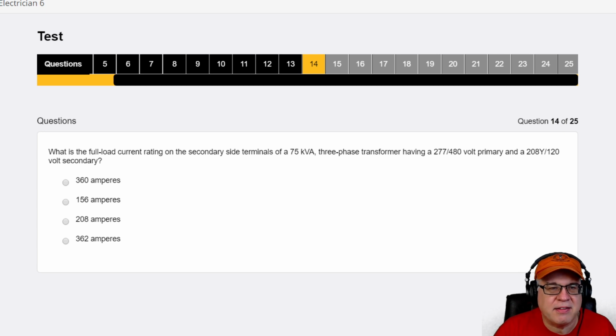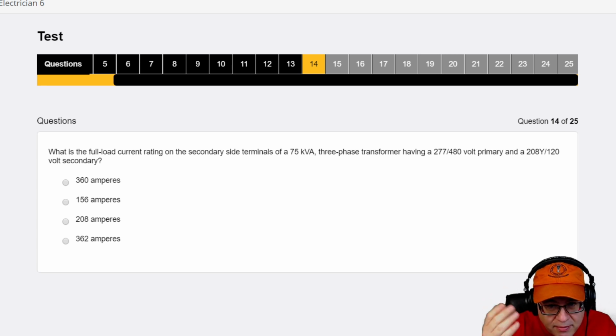It's asking about the full load current rating of the secondary, not the primary. So the secondary is 208/120, and it's 3-phase, so I've got 208. There's a shortcut to the 208 because it's 3-phase. First I'll do 208 times 1.732. Remember, 1.732 is the square root of 3, which represents 3-phase. Just remember that.